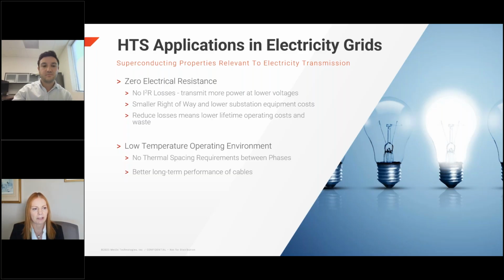So think a bit about that. If you look at how our grids have evolved over the last 50, 60, 70 years, as we needed to transfer more power across our grids, we found ourselves increasing the voltage level at which we did that. The reason was that by increasing voltage, we could reduce the current going through the line, and reduce the I squared R losses. Even though our infrastructure and switchgear were more expensive at higher voltages, and the right-of-way was much bigger, this was still more than compensated for by the reduction of I squared R losses. So this is how our grids have evolved to date.